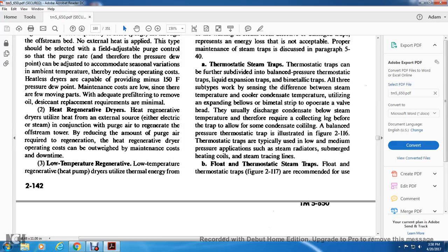Thermostatic steam trap. The thermostatic steam trap can be further subdivided into the balanced pressure type, the liquid expansion type, and bimetallic traps. All three subtypes work by sensing the difference between the steam temperature and the cooler condensate temperature, using a bellows or a bimetal strip operating the valve head. They usually discharge condensate below the steam pressure temperature, therefore requiring a collecting leg before the trap to allow for some condensate cooling. The balanced pressure thermostatic trap is illustrated in figure 2.11.6. Thermostatic traps are typically used for low-to-medium pressure applications such as steam radiators, submerged heating coils, or steam tracing lines.